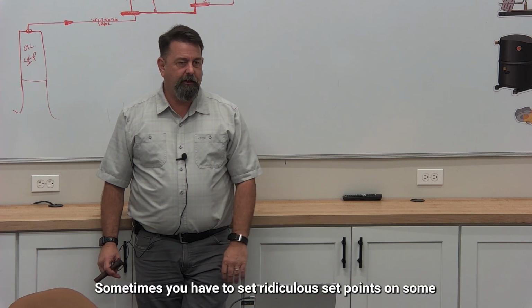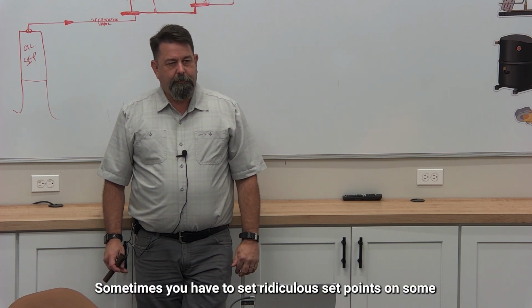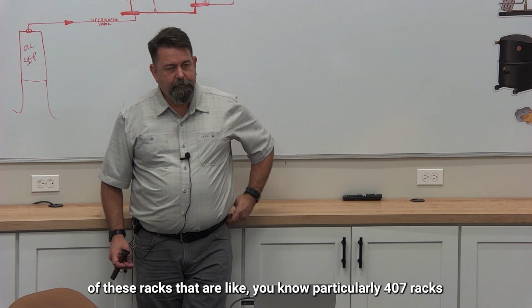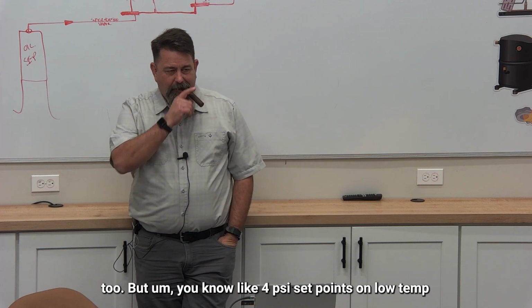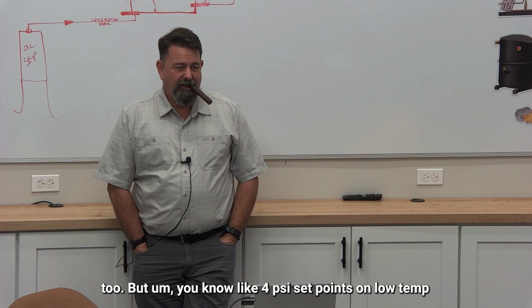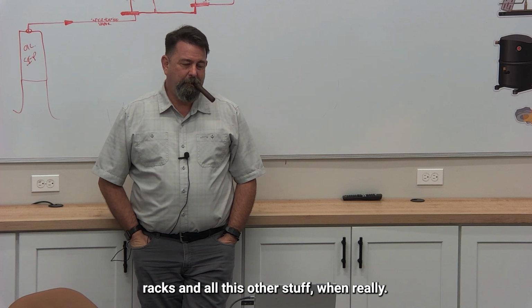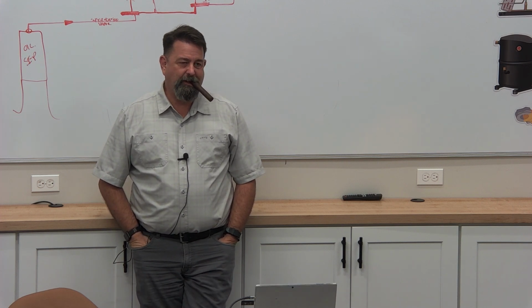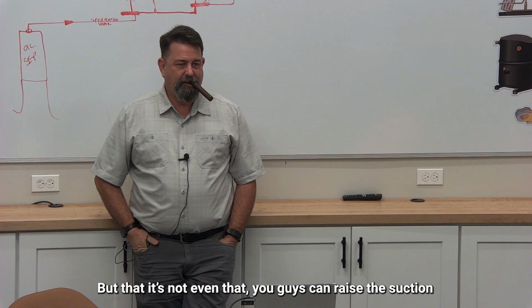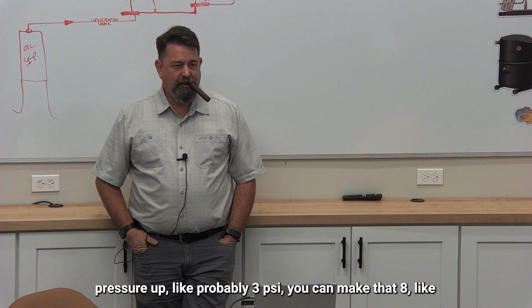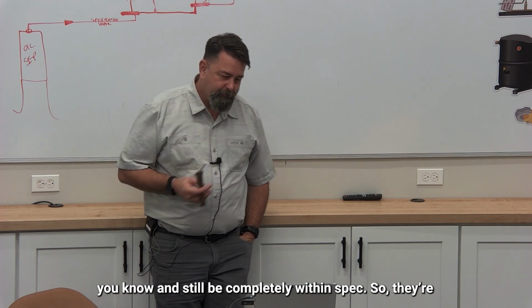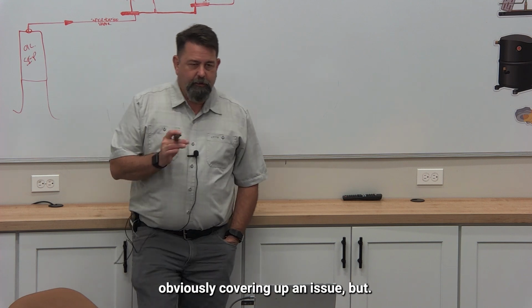Sometimes I see ridiculous set points on some of these racks, particularly 407 racks too, like 4 PSI set points on low temp racks and all this other stuff, when really minus 27s, yeah. But they're not even that. I'm like, you guys could raise the suction pressure up like probably 3 PSI. Like, you can make that 8, and still be completely within spec. So obviously they're covering up for an issue, but you know.